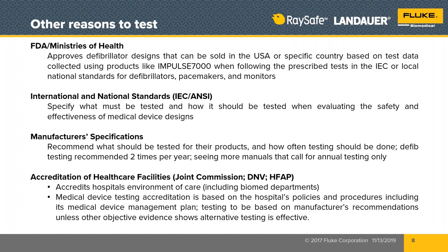Now, they also have accepted for those hospitals that have databased and have analyzed their failure rates to perhaps modify the frequency of inspection a little bit, but not about defibrillators or anything else that falls under the critical medical device category. Now, that certainly includes life support devices, and it includes life-saving devices like defibrillators and more. So if you think in your hospital that you can adjust down and just do once per year or once every 2 years looking at your defibrillator, guess again. That's not meeting the requirement.